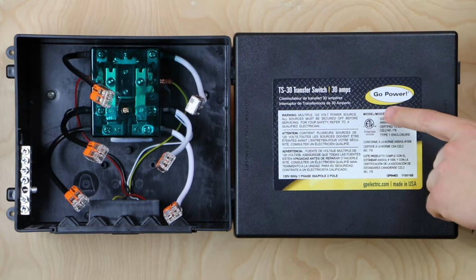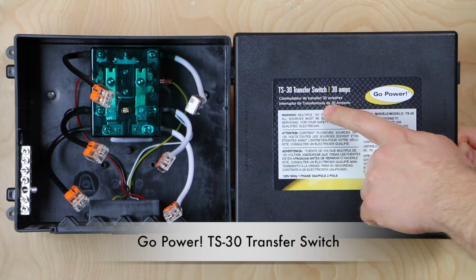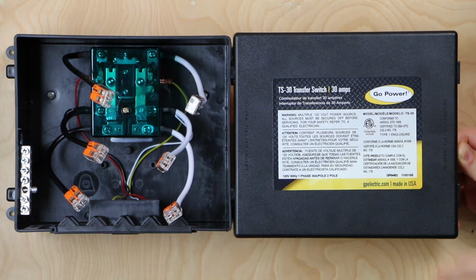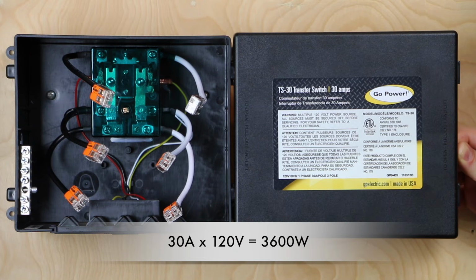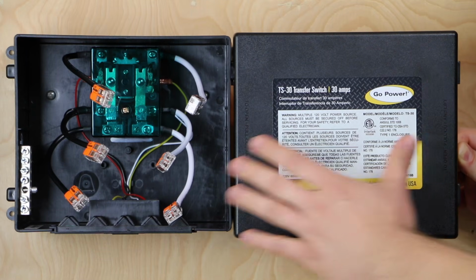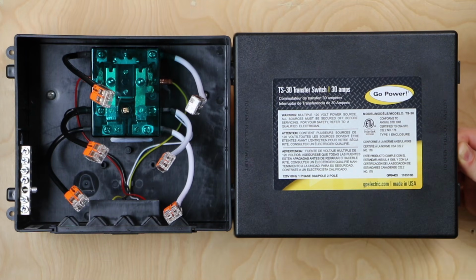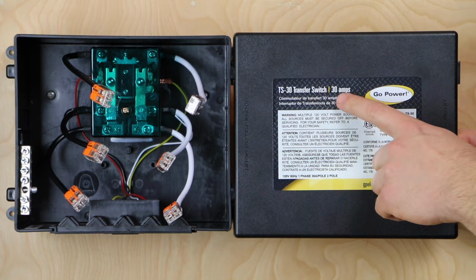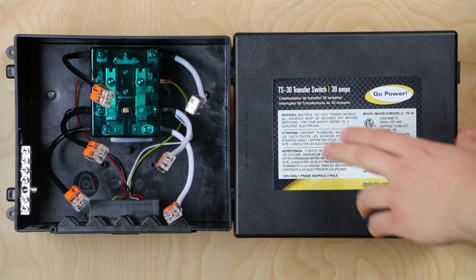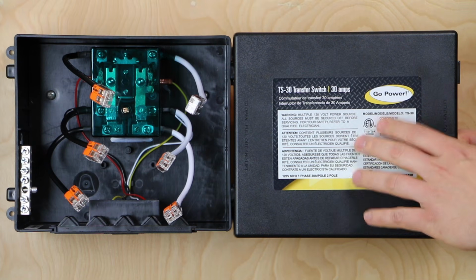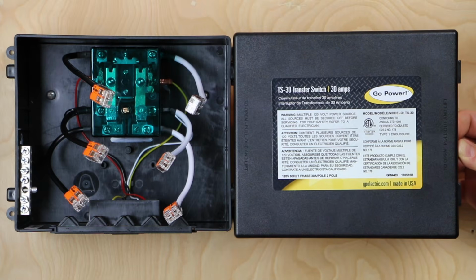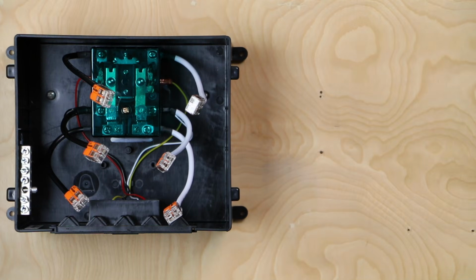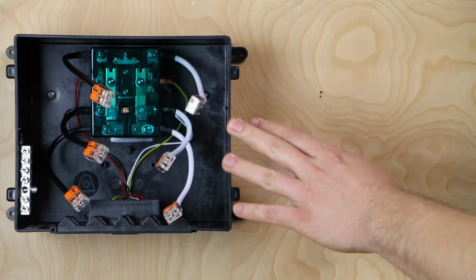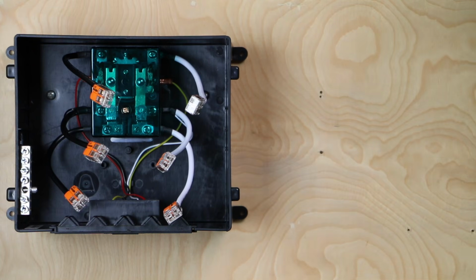To start out, I wanted to mention that we're using the GoPower TS-30 transfer switch. This is a 30 amp model. 30 amps multiplied by 120 volts for the power grid here in North America gives us 3,600 watts of power to charge our batteries and run our appliances. That is typically plenty for the camper vans that I build. They do make 50 amp transfer switches, but 30 amp is typically all I need, and I've used this model a couple of times.